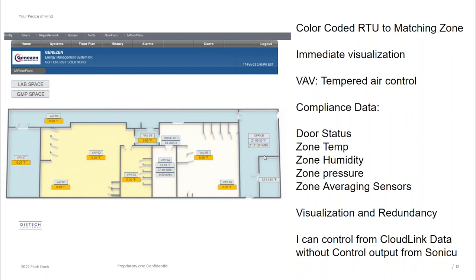We can animate those on alarms so they would go into red if they're an alarm. The one thing we're a big proponent of is if the alarm is not cleared, we still have it flashing. Even though it's normal, we still want that flashing to indicate there's been an incident or situation that requires documentation. In the data compliance world, documentation is everything. So if we're resolving an issue, we can track that at both the BMS and the Sonicu levels and never lose our compliance in that application.